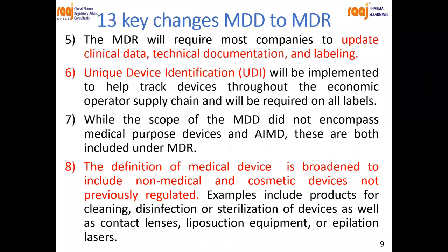While the scope of the MDD did not encompass medical purpose devices and AIMD, these are both included under MDR. The definition of medical device is broadened to include non-medical and cosmetic devices not previously regulated. So what does it mean? In MDD, which is the old standard, non-medical and cosmetic devices were not regulated, and those are included in this MDR.